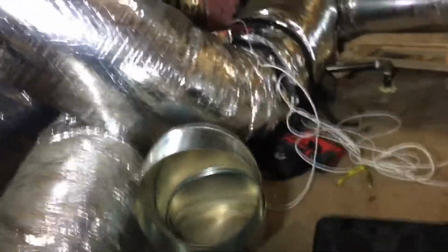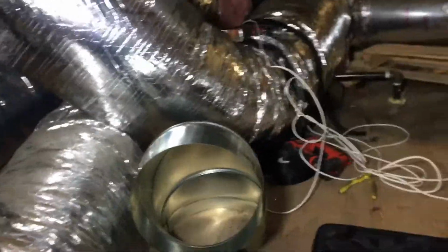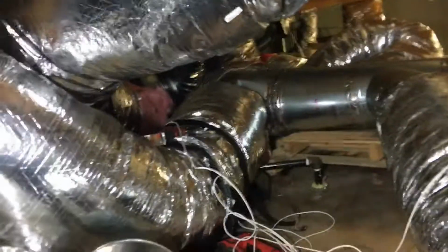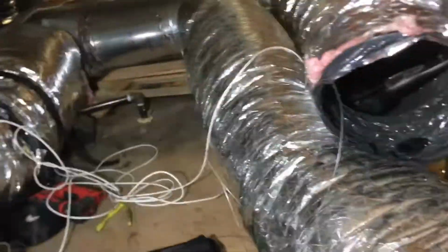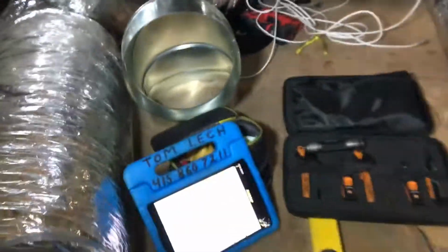The only problem was, it didn't matter how many guys were sent out here to keep checking charge and cleaning things and moving things — they never took care of airflow. That was the only problem: airflow. Airflow is king. You don't take care of airflow, I don't care what kind of magic squirt juice you stick into the system, you're not going to make it colder.